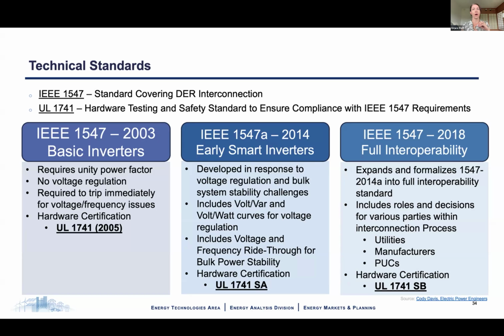On the bottom there, you can see UL, or explained at the top as well, but UL 1741 is a standard then that tests and certifies hardware products to ensure that they're meeting the IEEE requirements. This took me a long time to kind of parse out how this is all working together, but it is important. If you also, like me, need help understanding, IREC put out a really nice paper on the 1547 standard, and it notes that having these DER standards clearly defined really helps to increase interconnection efficiency, minimize confusion, and reduce costs overall.